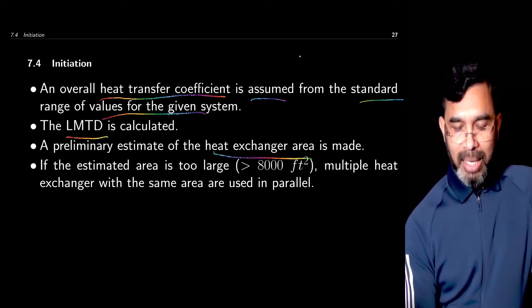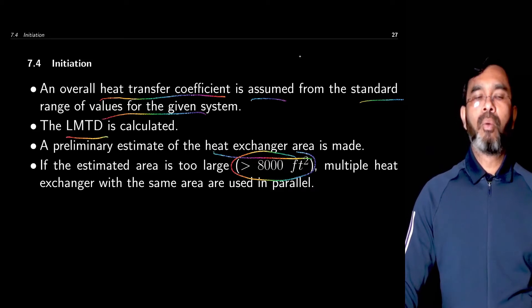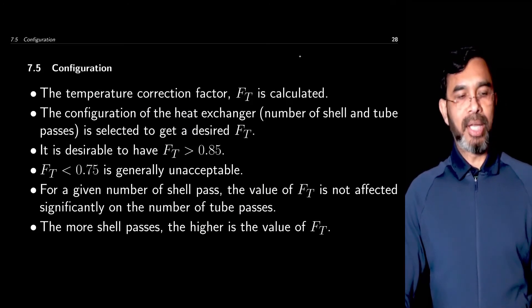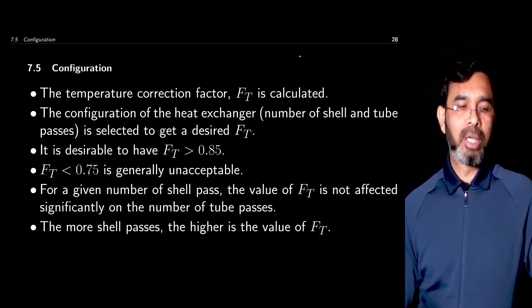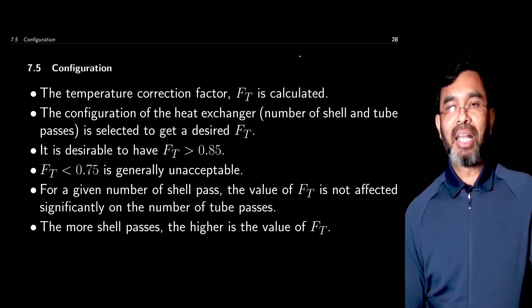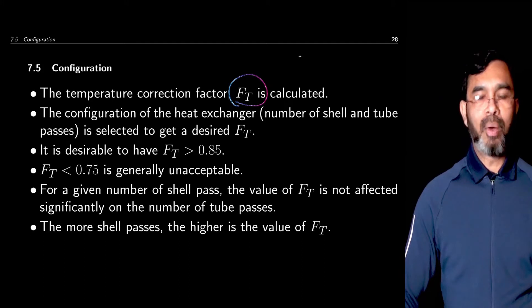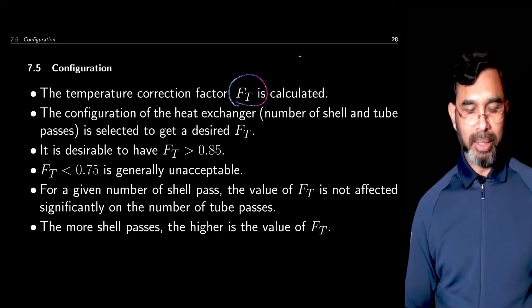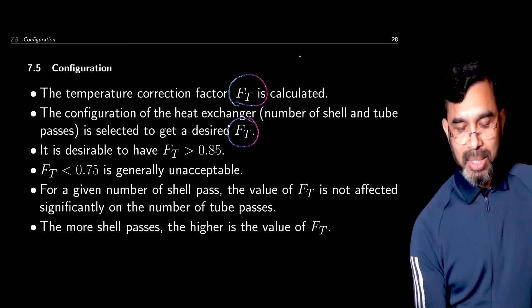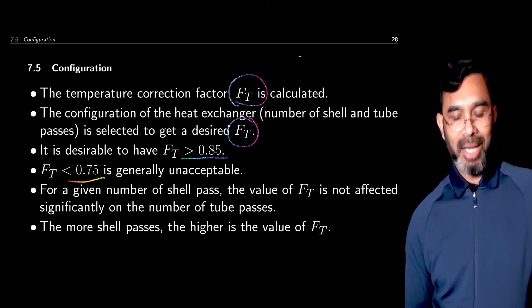If the area is too large — typically larger than around 8,000 square feet — then one heat exchanger is not enough and you need to use multiple units. For multi-pass shell and tube heat exchangers, the shell side can have more than one pass and the tube side can also have more than one pass. For those cases, the log mean temperature difference needs a correction factor FT. A desirable value is greater than 0.85, and if it is less than 0.75, it is typically considered unacceptable.